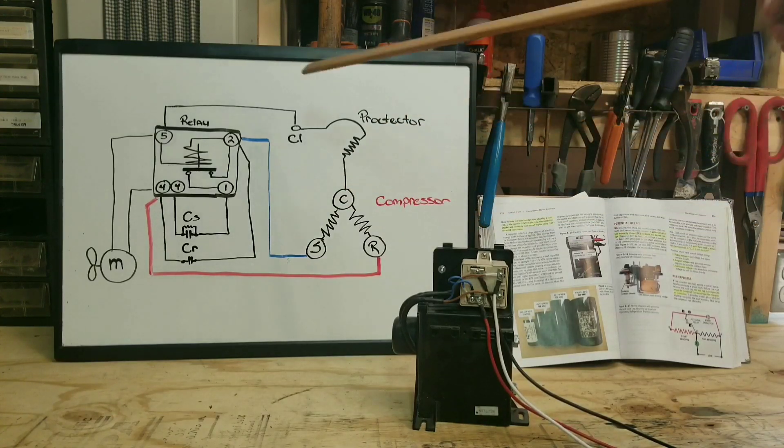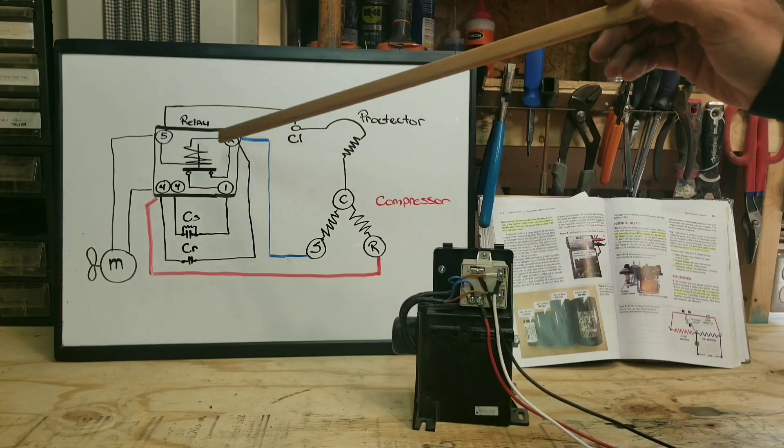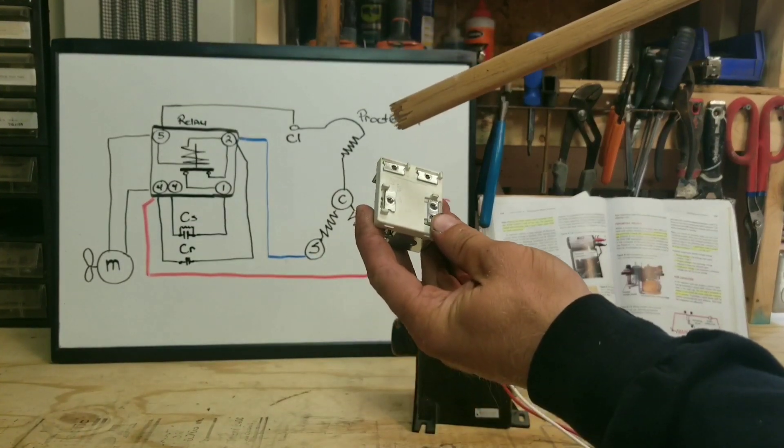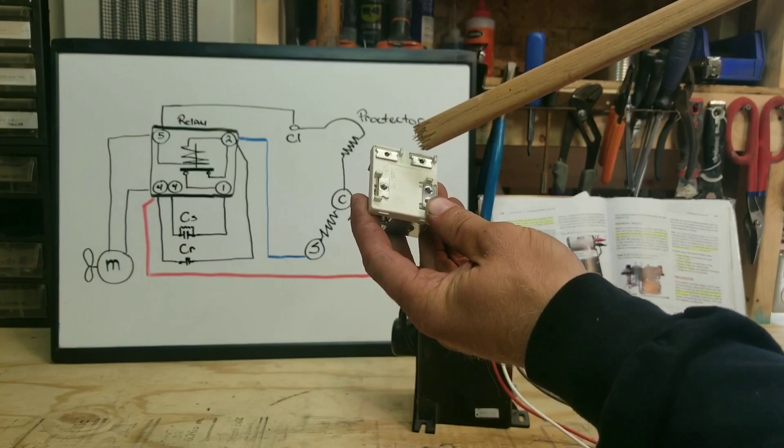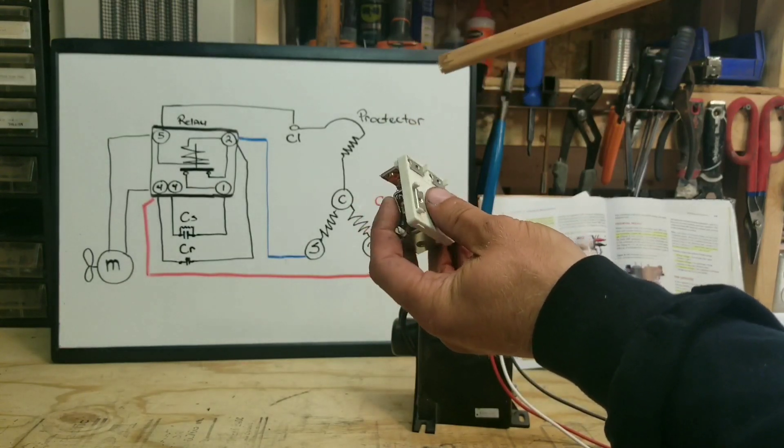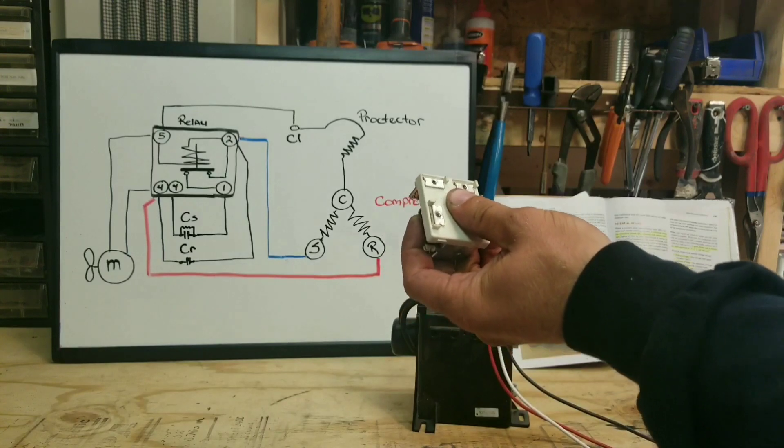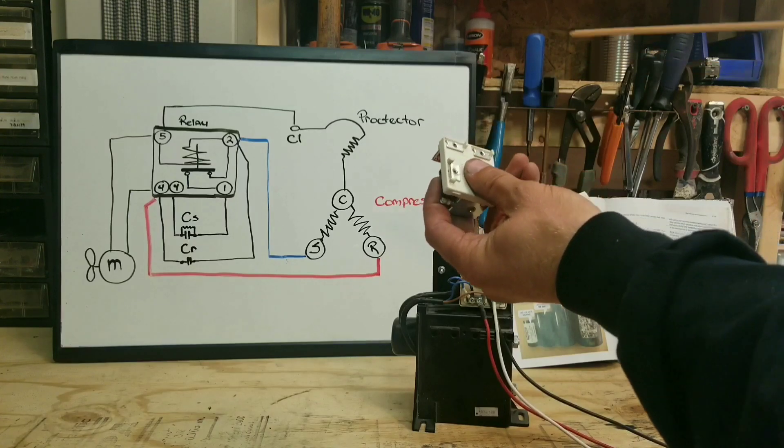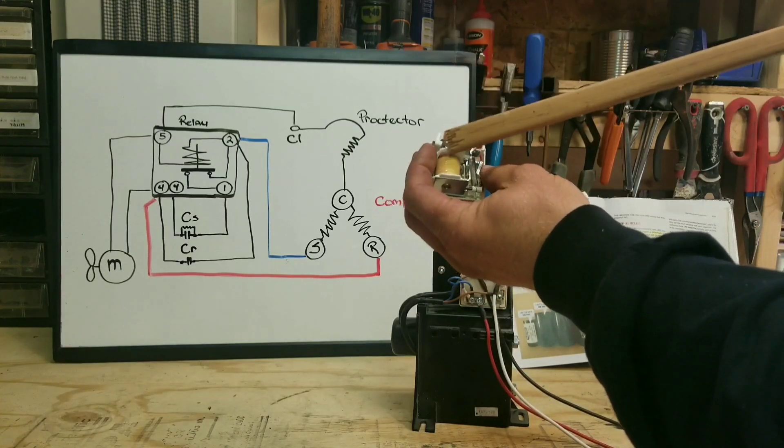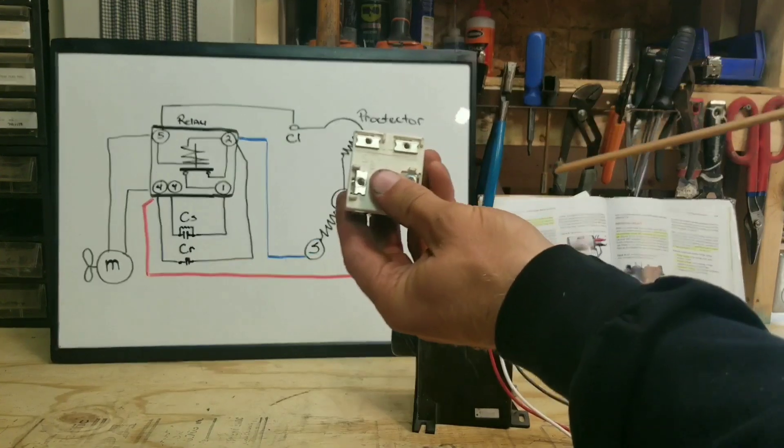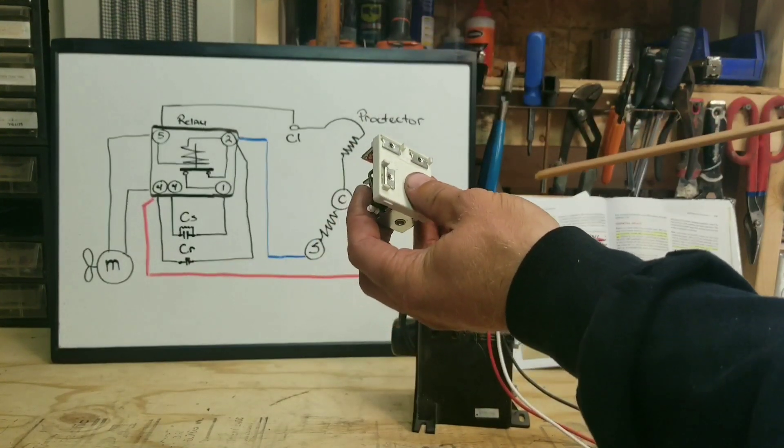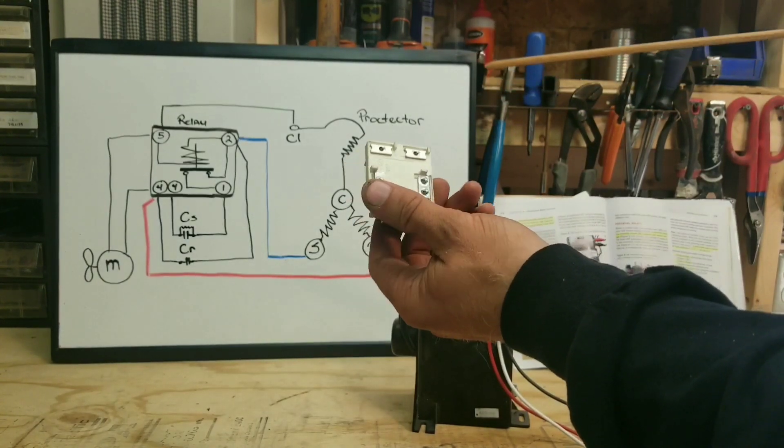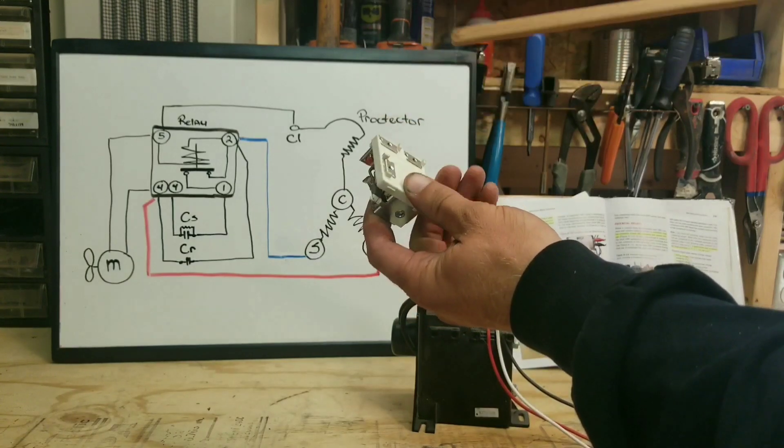And the best way to do that is, or the best way to test for that is, if you can take this relay off, unwire it, take it off, and then what you do is you just check between two and five, and you should have some sort of resistance. And that will vary depending on your actual potential relay, because they're manufactured by many different companies. But you should have some sort of resistance through this solenoid. So if you suspect that it's bad, you suspect that the start winding, or excuse me, that the start capacitor and the start winding are not getting taken out of the circuit, you can test across that and you can see if that solenoid is any good.